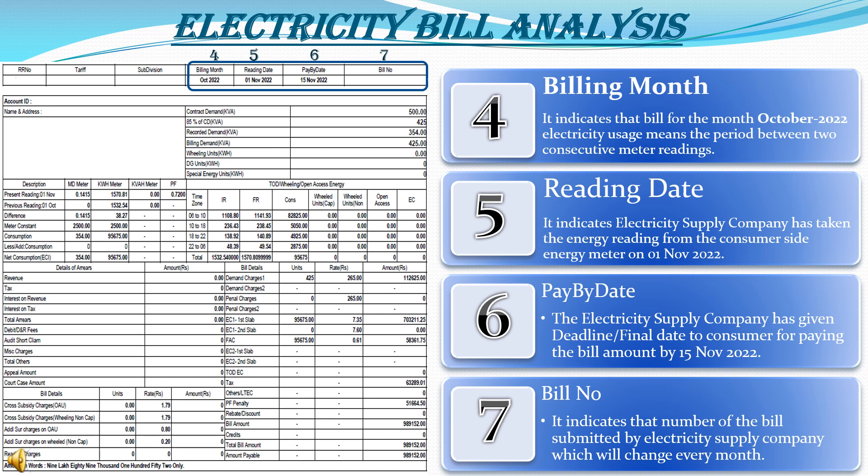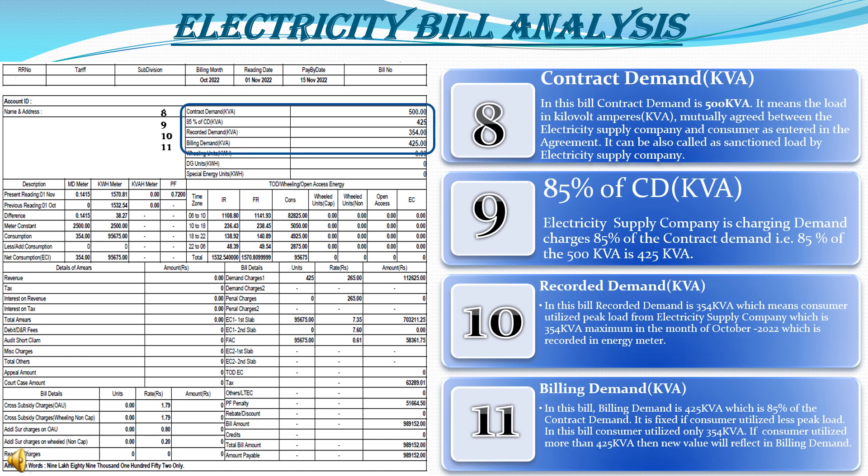The billing number indicates the number of the bill submitted by the electricity supply company, which changes every month — this is for the electricity supply company's reference. Contract demand is a very important term in the electricity bill. In this billing, the contract demand is mentioned as 500 KVA — the load in KVA mutually agreed between the electricity supply company and the consumer as entered in the agreement. It can also be called the sanctioned load by the electricity supply company.